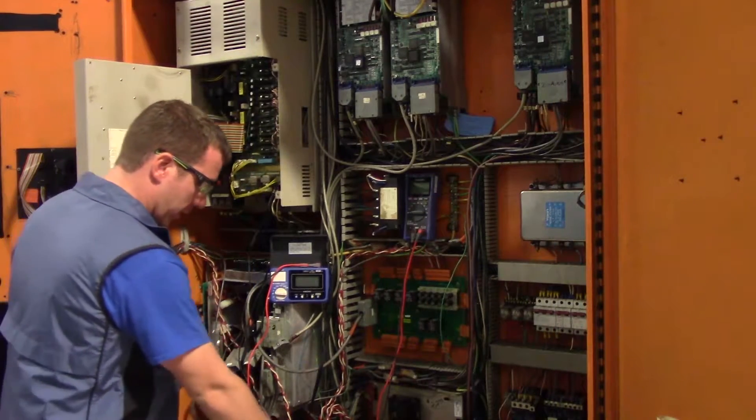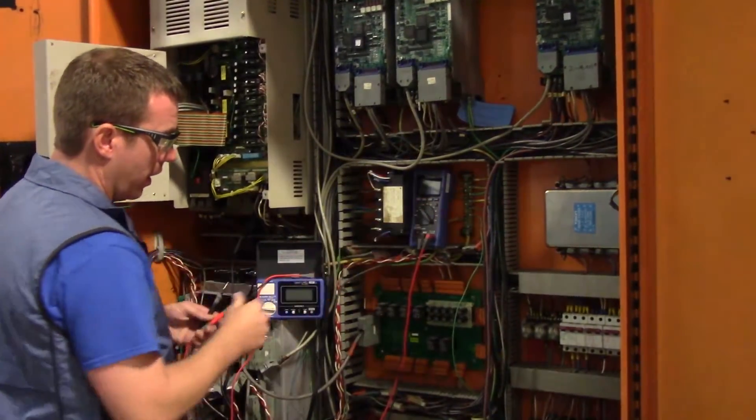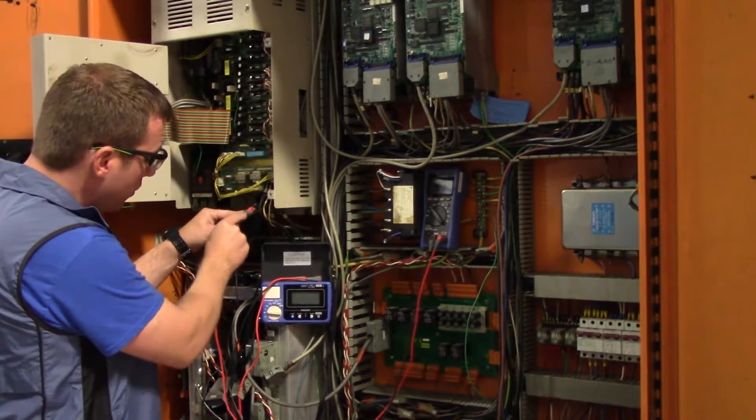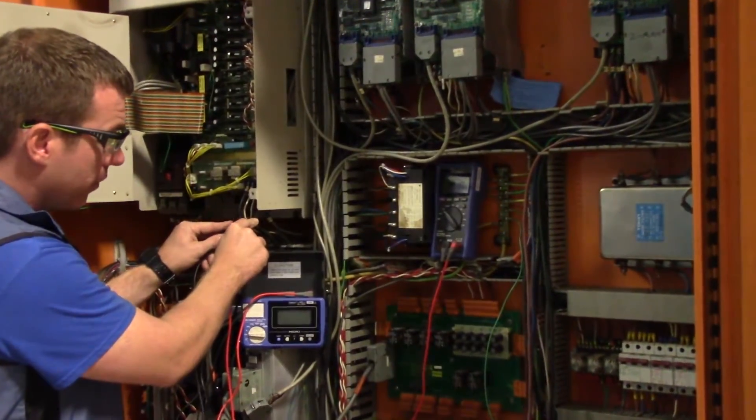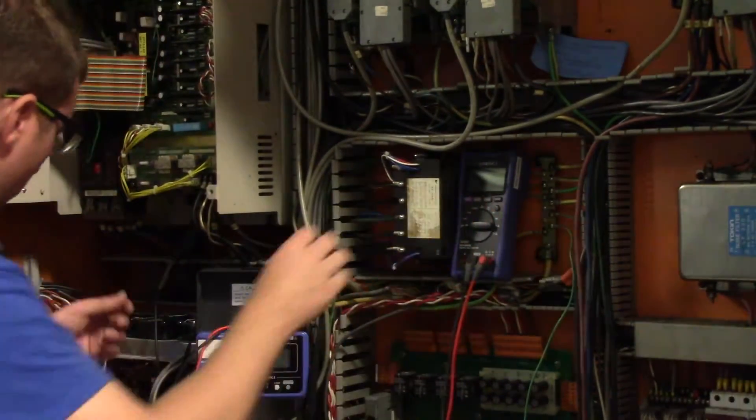Okay, so the first thing that we're going to do is take our multimeter and we're going to check it, set it to the AC function. And we're just going to triple check between U, V, and W on the output of the drive. And we have nothing there. So the drive is safe to work with.